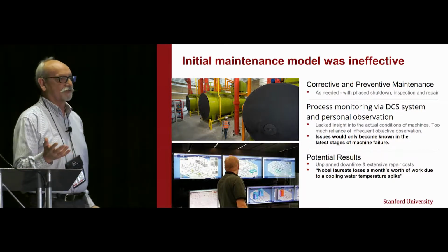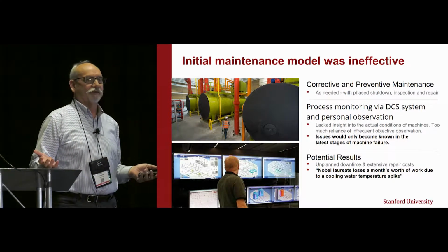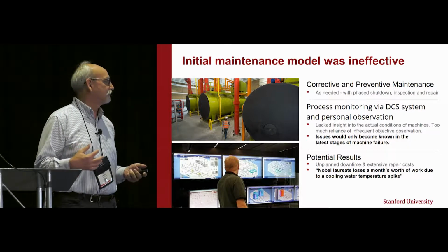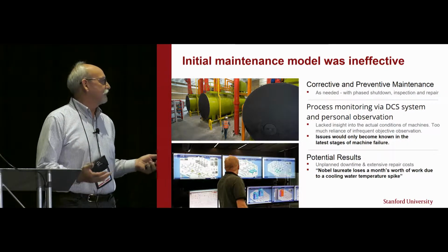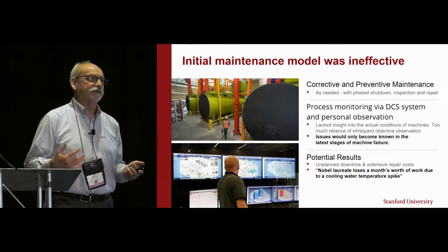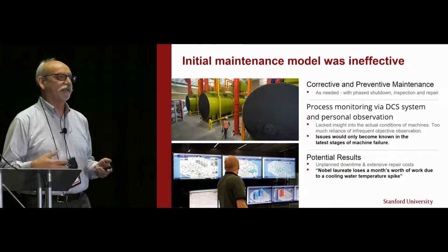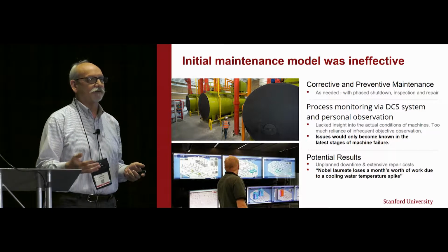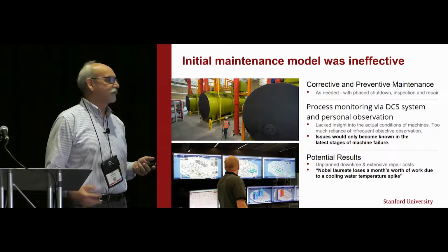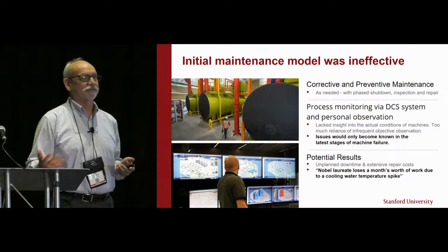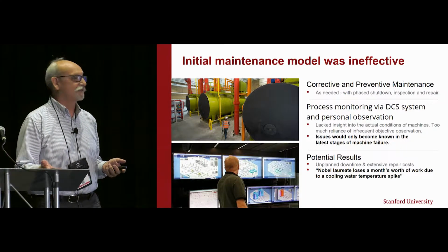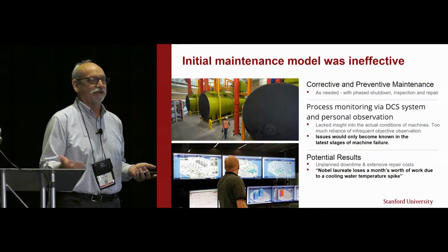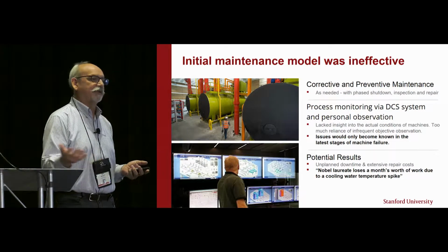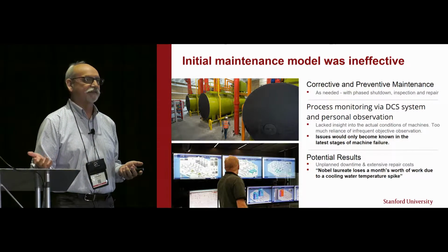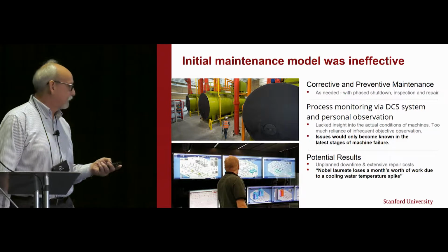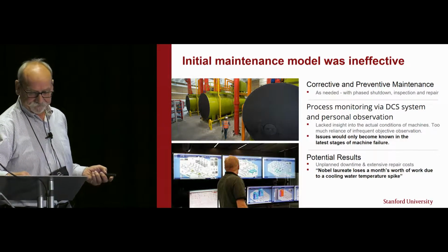Everything was based on a control room. You get an alarm, some process alarm happens. You have techs walking around; they'll respond to the alarm, and if there's a problem with the machine, they'll fill out a work order and call somebody to go look at it. It's very subjective. A lot of times it depends on who the operator is, whether he catches it and calls you, and it depends on who's the tech making the rounds, whether he happens to walk by a pump when it's making a noise or notices a leak before it's too late or becomes a bigger problem.